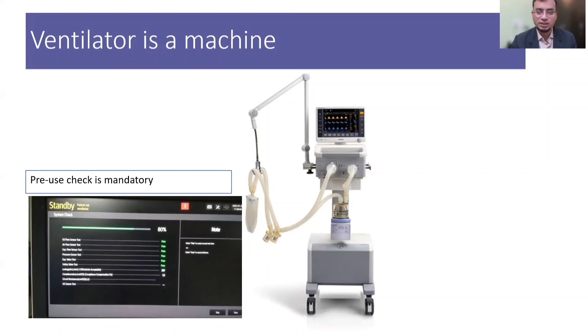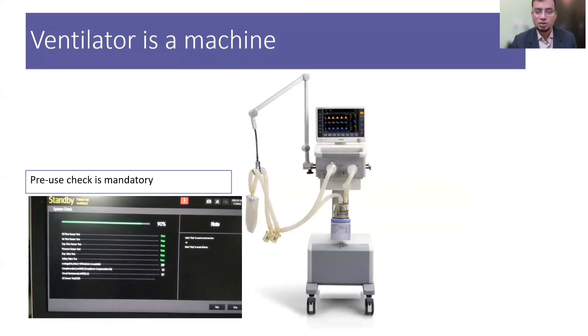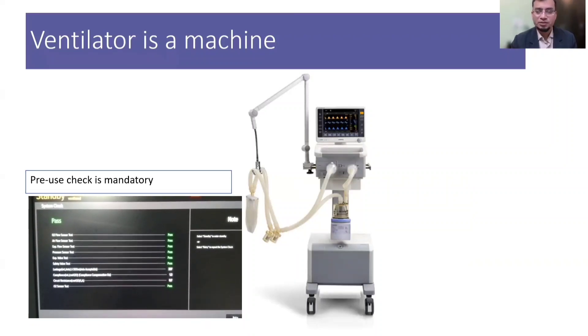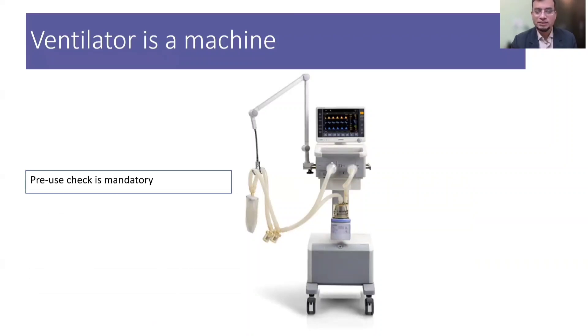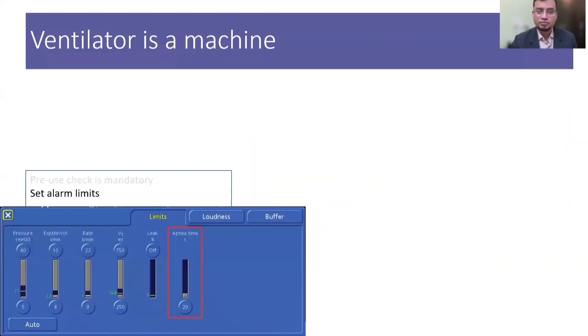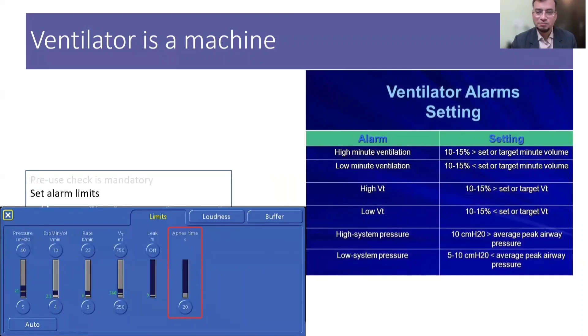The pre-use check is usually done at the time of humidifier or circuit setup, and any time the circuit is changed or modified, a pre-use check must be done. It is vital that the alarms be set appropriately; otherwise there is potential for significant morbidity and mortality. Setting limits on rate, pressure, and volume is just as important as the ventilator settings, so you must set the ventilator alarms very carefully.